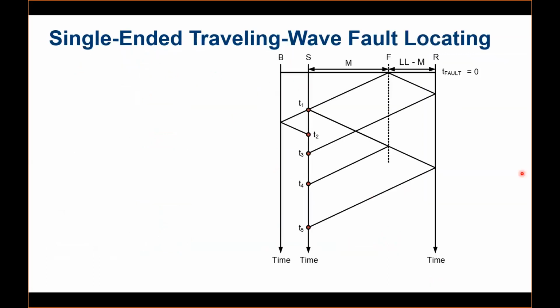One more application for this traveling wave is the fault location. We have two kinds of fault location available, depending on how many relays you have in one feeder. If you have a relay only on a single end, we call this the single-end traveling wave method, and it will not be connected with a remote relay. So if you have only one relay at one of the ends of the line, you can implement traveling wave fault locating, that's the single-ended method.